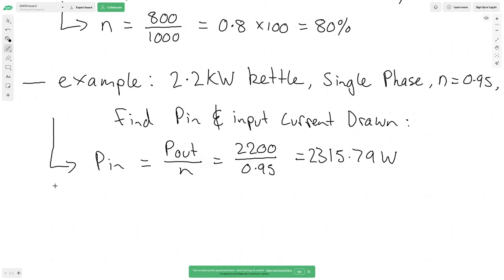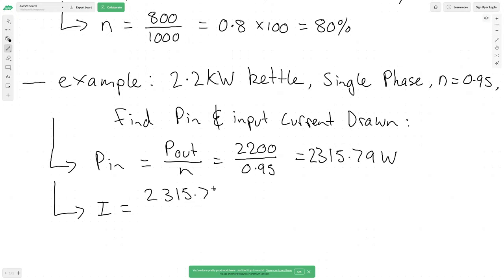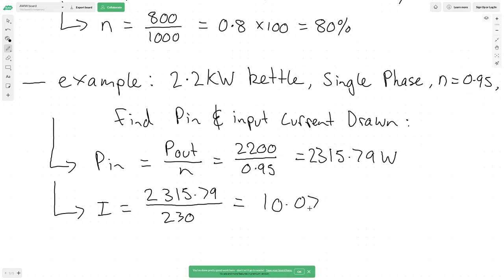Now find the current drawn. We use I equals P-in divided by V-supply, so that's 2315.79 divided by 230, which gives us 10.07 amps. We use P-in here — the total power consumed — because that represents all the current actually flowing through the cable.